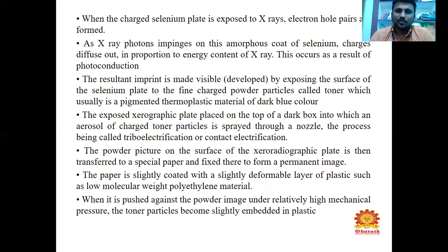The exposed xeroradiographic plate is placed on top of a dark box into which an aerosol of charged toner particles is sprayed through a nozzle, the process being called triboelectrification or contact electrification. The powder picture on the surface of the plate is then transferred to a special paper and fixed there to form a permanent image.